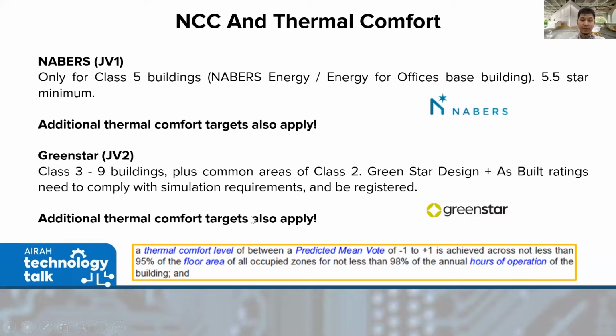What do these thermal comfort targets look like? A thermal comfort level between PMV of -1 to +1 - a bit more lenient than ASHRAE 55's -0.5 to +0.5. It must be achieved across not less than 95% of the floor area, so they also include coverage: it needs to cover 95% of the floor area.